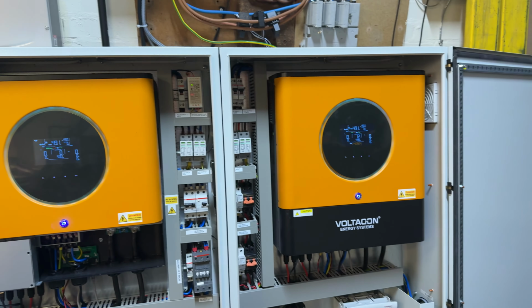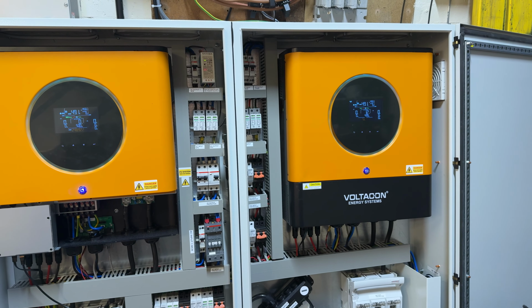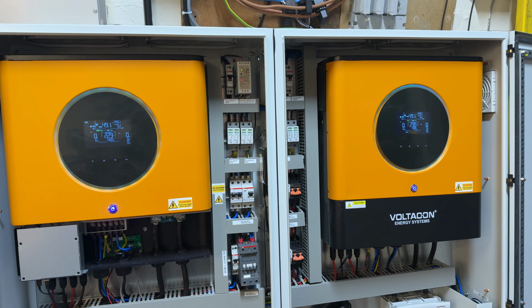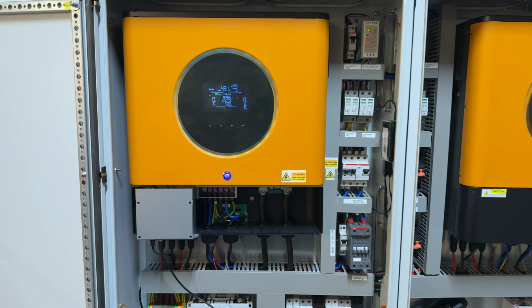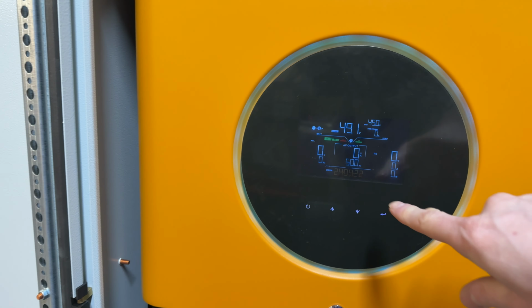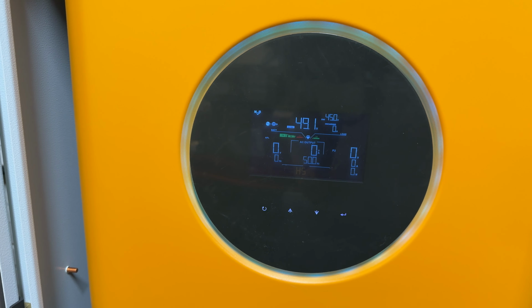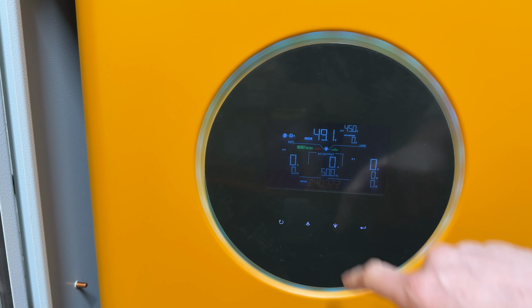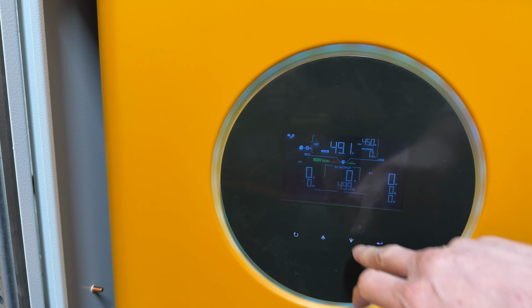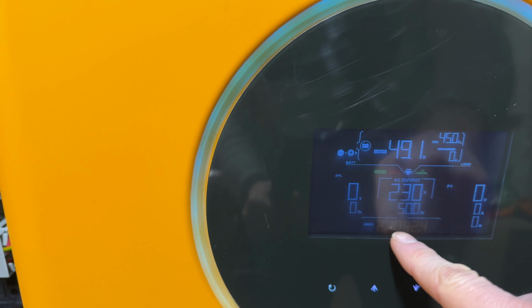This is a 16 kilowatt off-grid cabinet. We pre-installed two off-grid inverters, 8 kilowatt each. As you can see, the inverters are connected in parallel. This one is the master inverter, the indication HS is flashing, and this is the secondary inverter with indication SL.